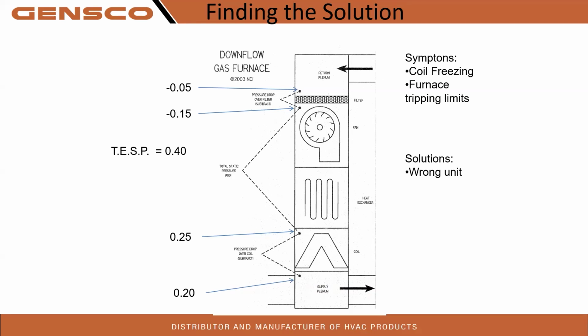So what if we have five ton of ductwork with a 3-ton furnace? Oversized ductwork is not good either. Don't see that too much, but we have seen where there's too big a ductwork and we don't have enough static pressure to work efficiently. That could be blowers plugged too. We always want to check amperage. We want to see what that actual blower motor voltage is getting.